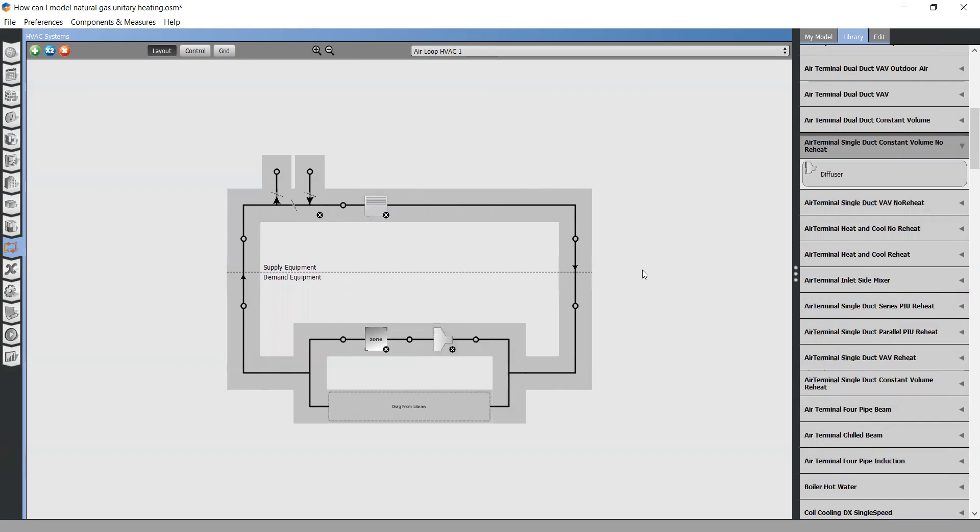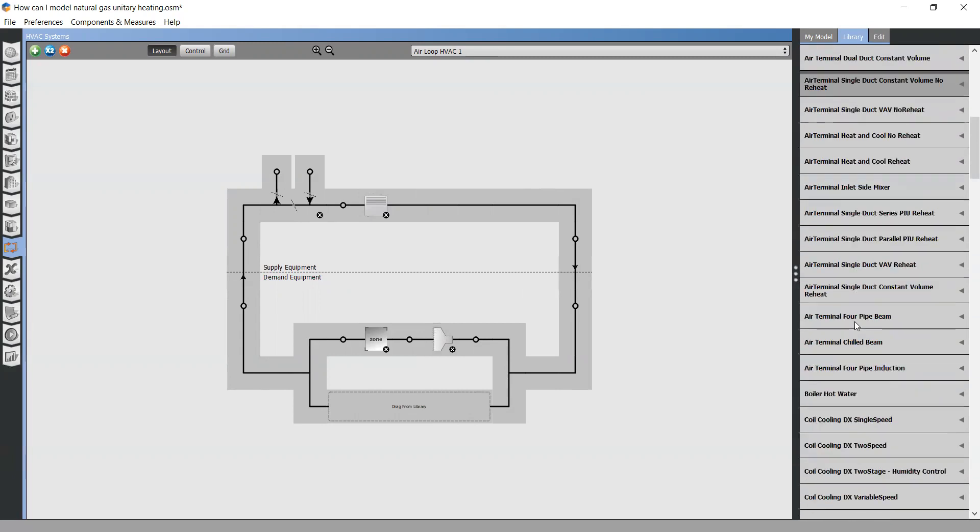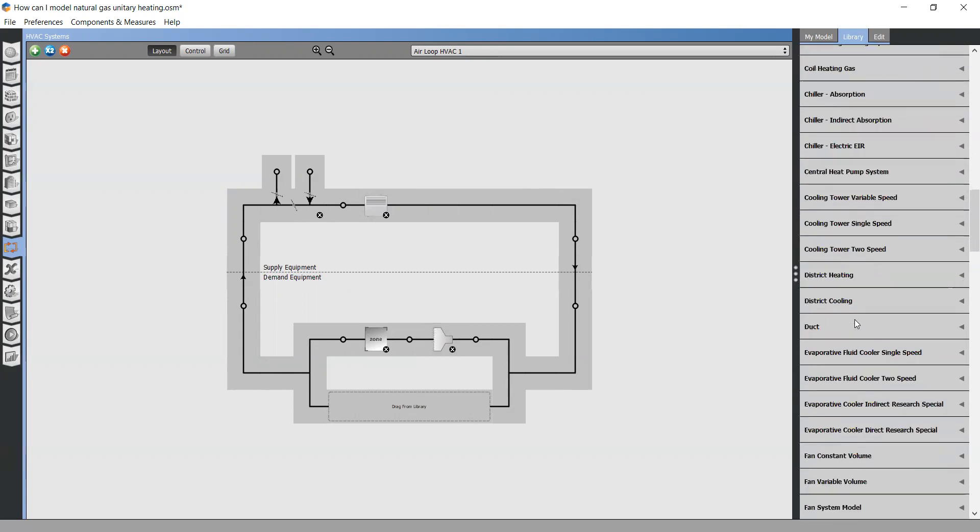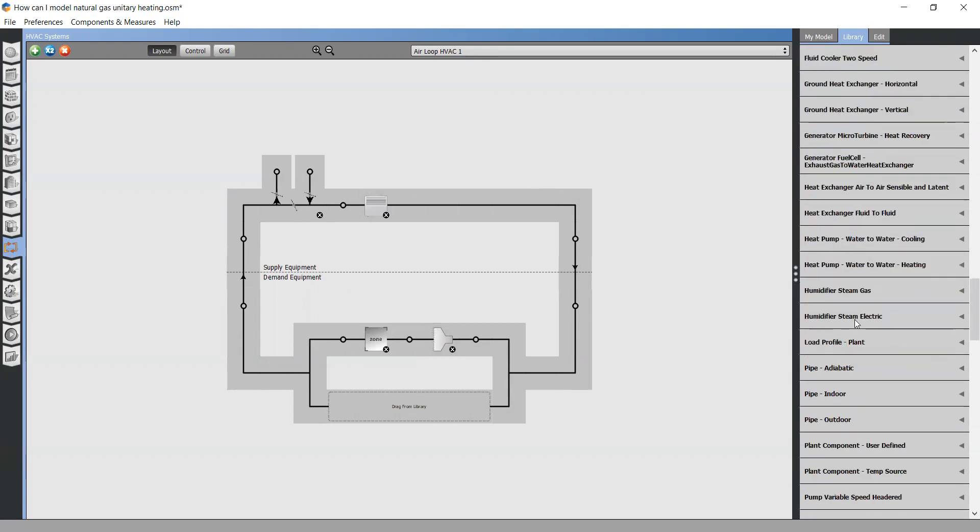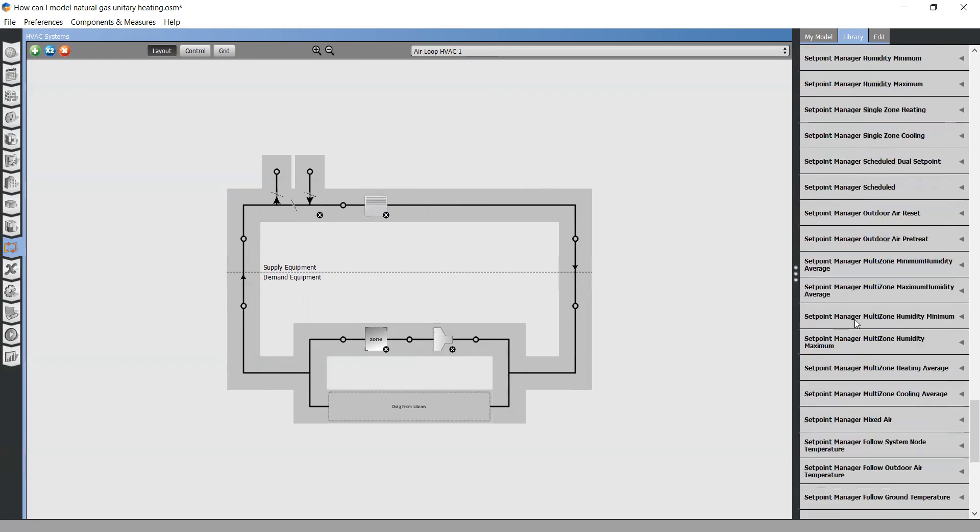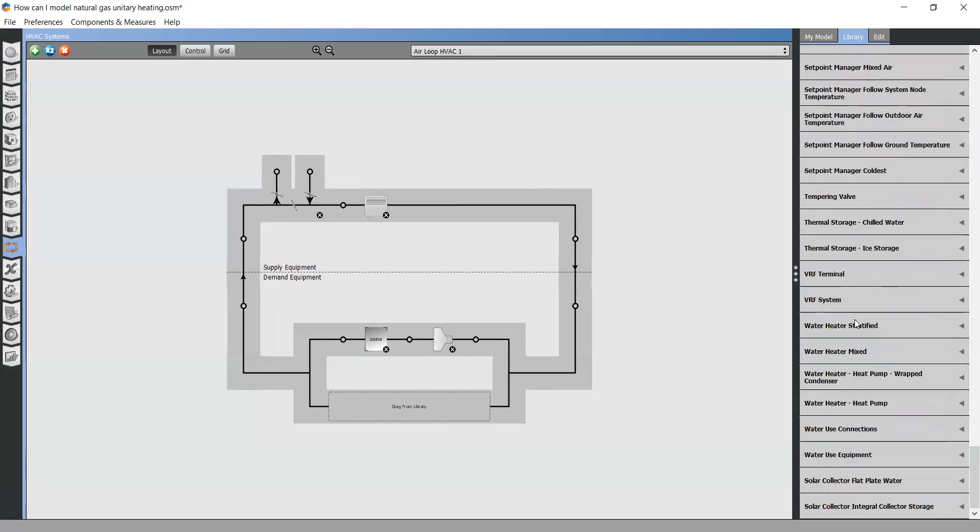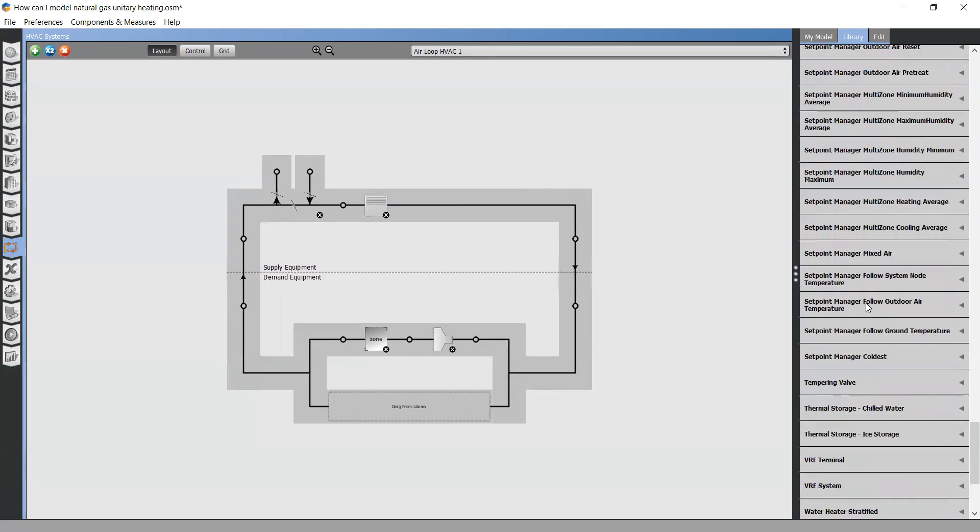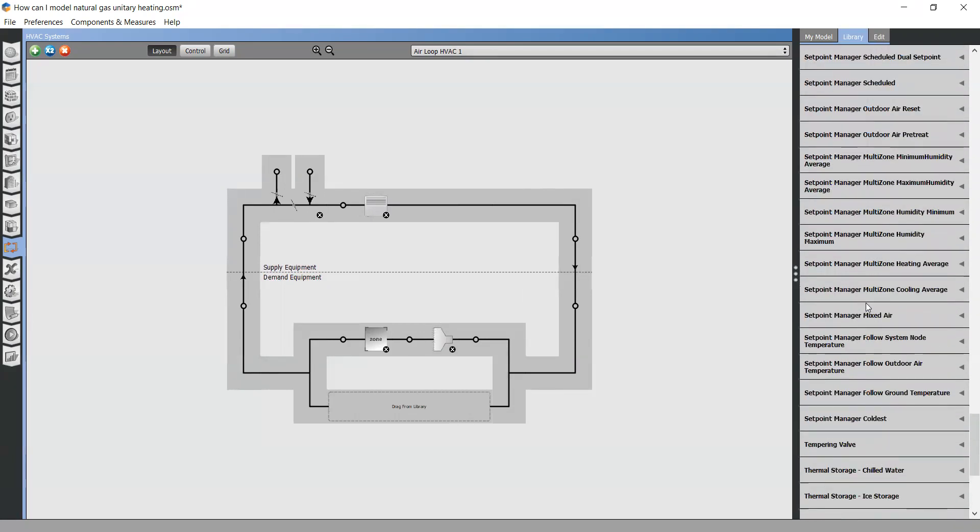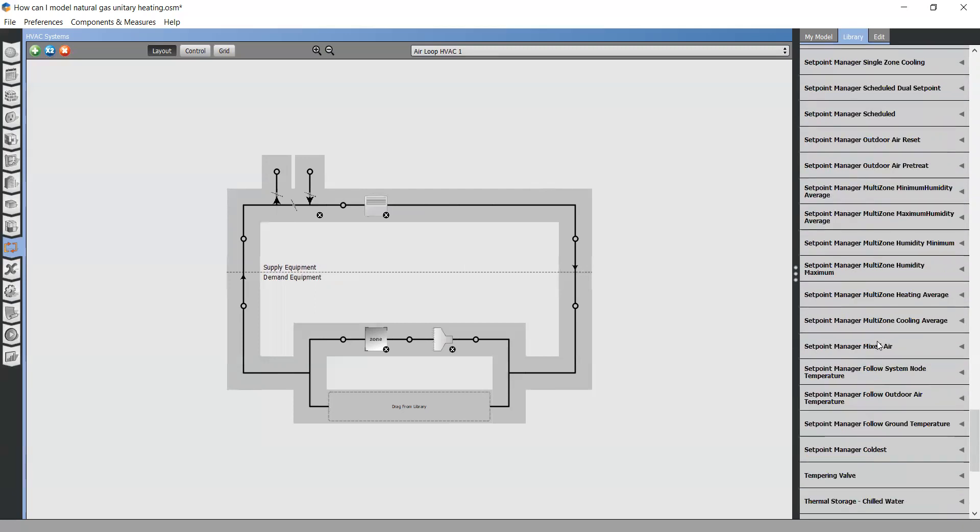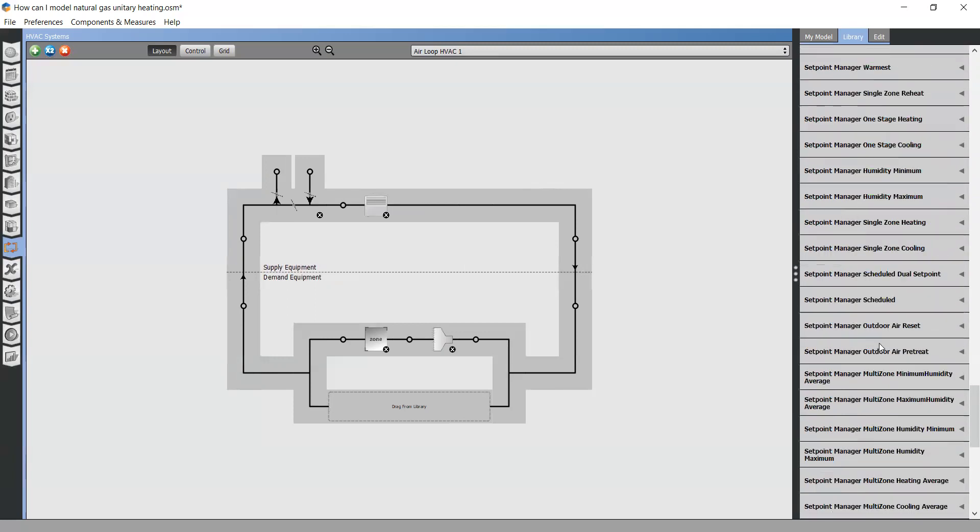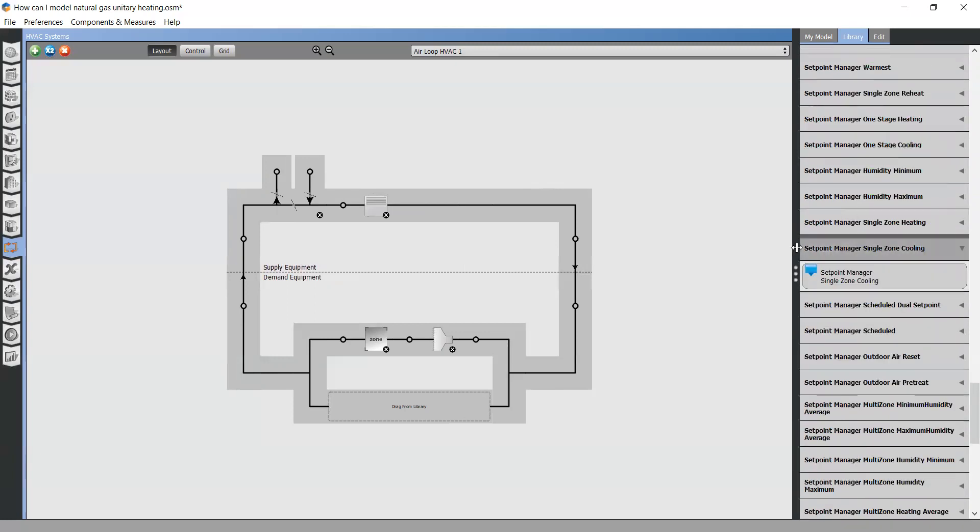Make sure there is a set point manager. The most appropriate one. Always searching from the library. Drag and drop set point manager for single zone. Set point manager single zone cooling. Drag and drop to your air loop.